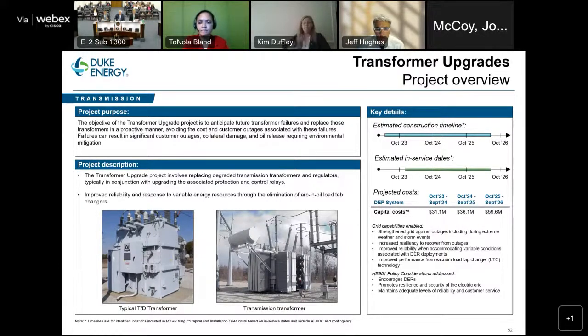This project also includes regulators. Regulators, substation regulators specifically, are very similar to transformers. Whereas transformers transform voltage over large areas, regulators control voltage over a very tight band, so plus or minus 1 volt in some cases. And we are obligated to maintain this voltage out on our systems. And you heard a little bit about voltage regulation earlier from Mr. Guyton. A regulator in a transmission substation controls the voltage for all the circuits leaving that station. And we'll look at an example of that on the next slide.